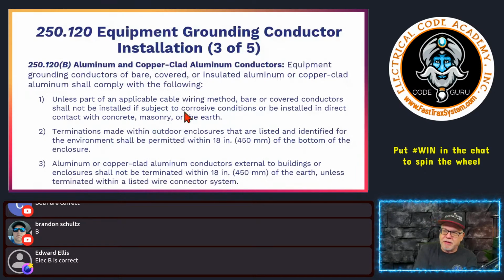All right, so let's talk about equipment grounding conductors when it comes to aluminum or this other type of conductive material, which I won't discuss, okay? I'm going to just talk about aluminum, okay? It says equipment grounding conductors of bare, covered, or insulated aluminum or that other conductor shall comply with the following, okay? Unless part of an applicable cable wiring method, bare or covered conductors shall not be installed if subject to corrosive conditions, or to be installed in direct contact with concrete, masonry, or the earth. That should go without saying. So equipment grounding conductors, unless they're part of some wiring method that's already been evaluated and approved for the location where it's going to be, right? Other than that, what we're not going to have is aluminum or this other type of conductor installed where it is subject to corrosive conditions, or installed in direct contact with concrete, masonry, or the earth.